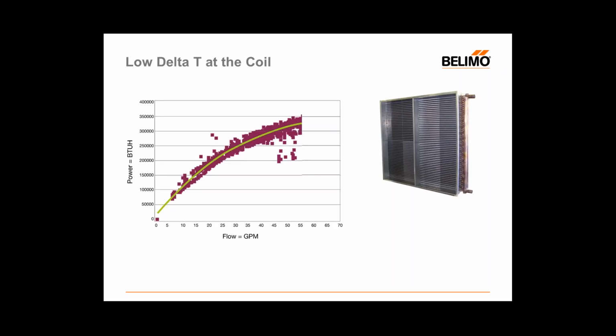As we increase the volumetric flow rate, we also increase the linear velocity of the water, and that molecule of water now moves through the coil faster. So as we increase flow going left to right, we see that curve starts to flatten out because each molecule of water spends less and less time in the coil. Even though there's more molecules, obviously volumetrically we're increasing the number of molecules, they're transferring heat less and less efficiently as we increase the flow rate.